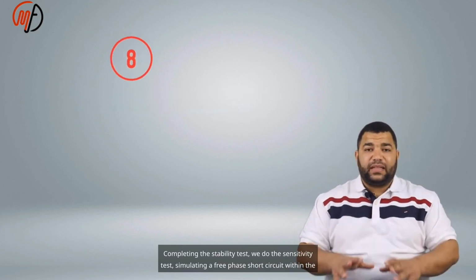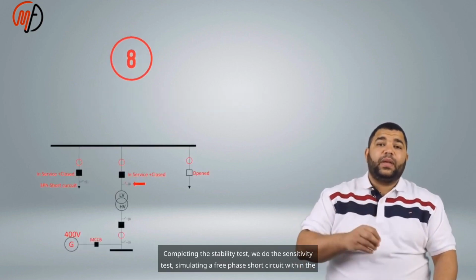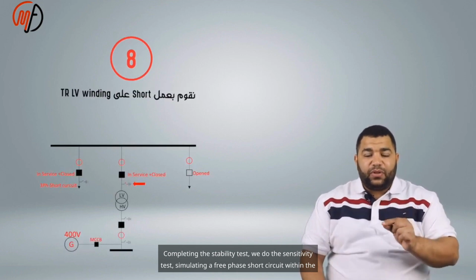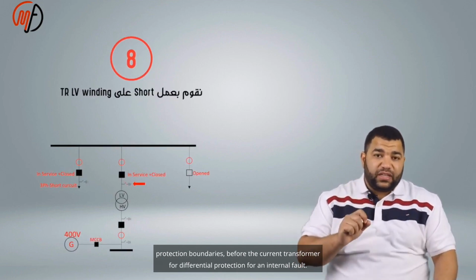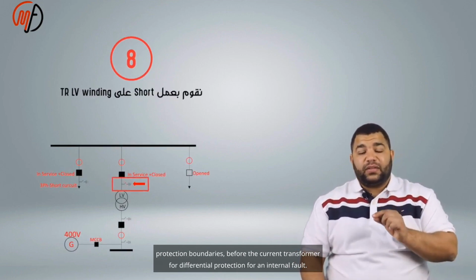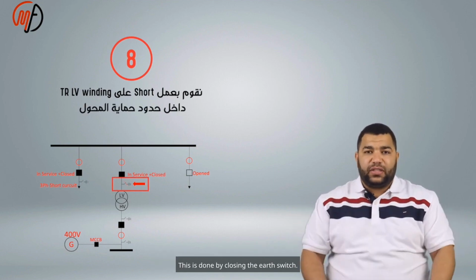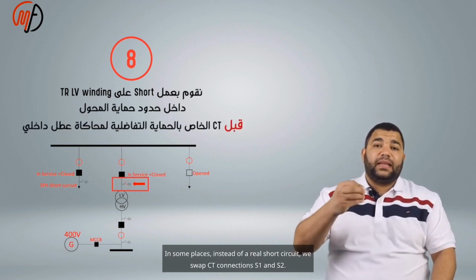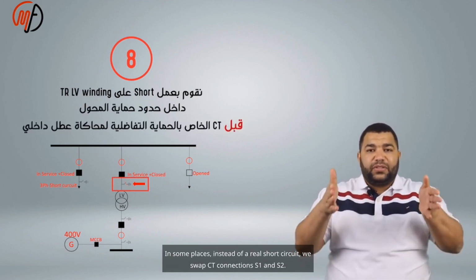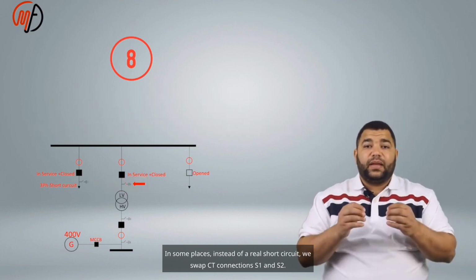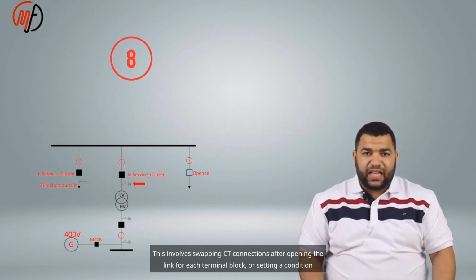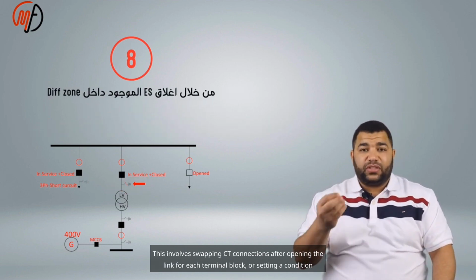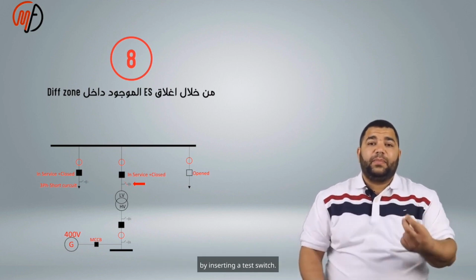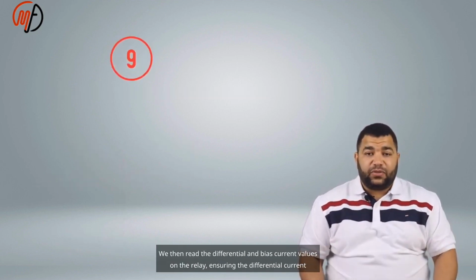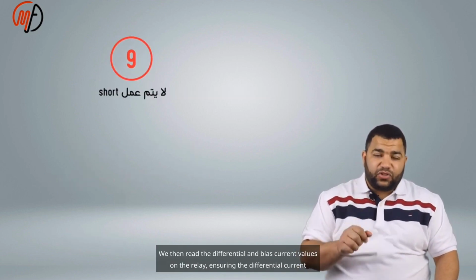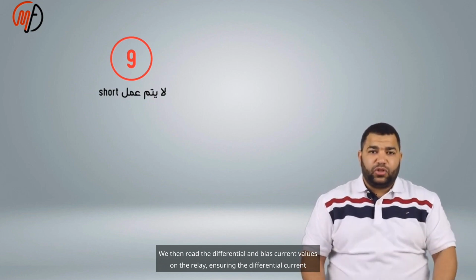Completing the stability test, we do the sensitivity test, simulating a three-phase short circuit within the protection boundaries, before the current transformer for differential protection, for an internal fault. This is done by closing the earth switch. In some places, instead of a real short circuit, we swap CT connections S1 and S2. This involves swapping CT connections after opening the link for each terminal block, or setting a condition by inserting a test switch. We then read the differential and bias current values on the relay, ensuring the differential current increases for an internal fault.